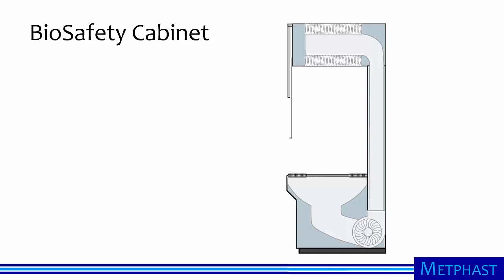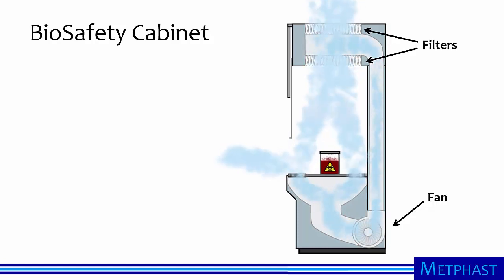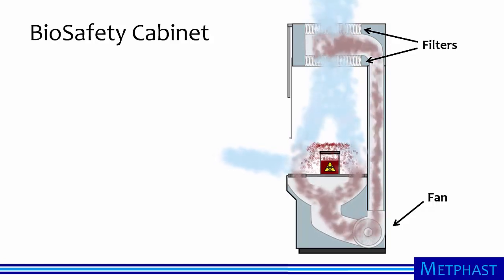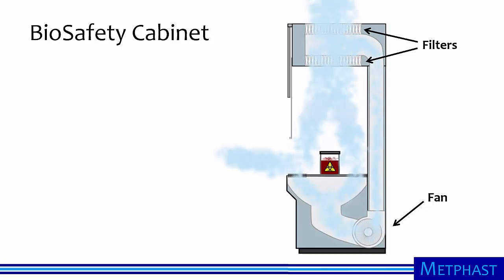A biosafety cabinet is another common enclosing hood specifically designed to handle hazardous biological materials. In this animation, we show a class 2 biosafety cabinet. A fan pulls air from the workspace floor, pushing it through high efficiency particulate air filters — HEPA filters. Some of the clean air exhausts to the room and some flows downward. Contaminated air from biohazardous materials is simultaneously pulled and pushed downward and then cleaned. This simultaneous push and pull of air eliminates most of the adverse recirculation patterns typical of traditional chemical fume hoods.